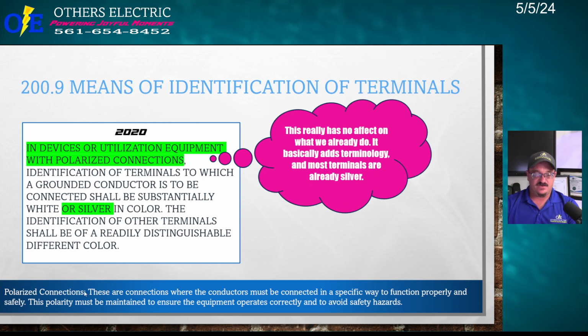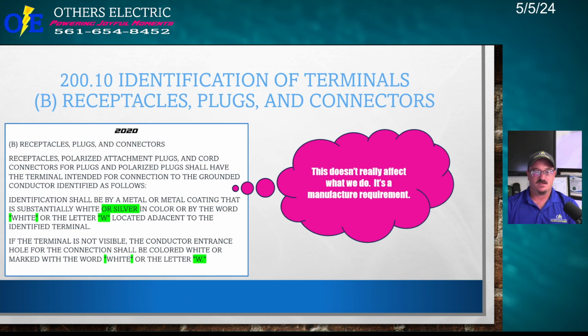And here's a definition of polarized connection. Polarized connections, these are connections where the conductors must be connected in a specific way to function properly and safely. This polarity must be maintained to ensure the equipment operates correctly and to avoid safety hazards. So that's what they added with polarized connections. And basically, polarized connections, if it requires a hot and a neutral to run, right? If it doesn't require polarized connections, like A phase and B phase on a 120/240 volt system, it's not polarized.